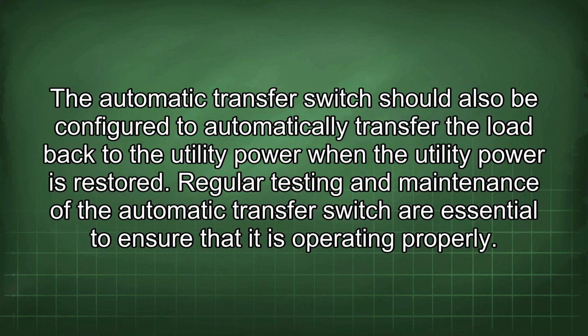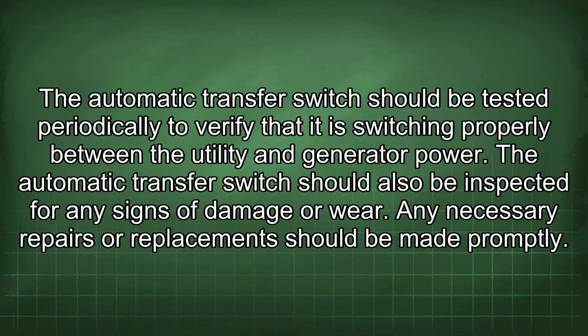The automatic transfer switch should also be configured to automatically transfer the load back to the utility power when the utility power is restored. Regular testing and maintenance of the automatic transfer switch are essential to ensure that it is operating properly. The automatic transfer switch should be tested periodically to verify that it is switching properly between the utility and generator power. The automatic transfer switch should also be inspected for any signs of damage or wear. Any necessary repairs or replacement should be made promptly.